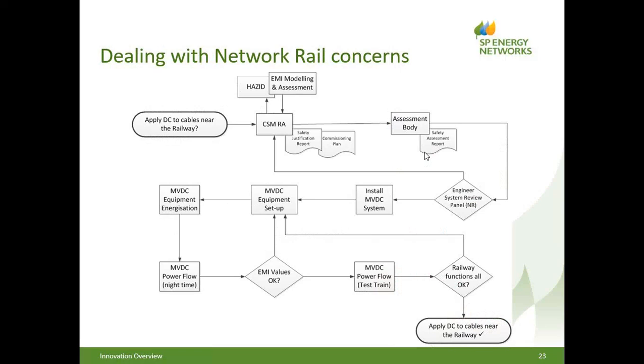So what we've got to do is undertake the common safety method risk assessment. That involves HazID workshops, and the output of this is to come up with a safety justification report, which also needs to include a commissioning plan of how we intend to bring the equipment online. And factoring into that very heavily is EMI modelling and assessment of the potential effects of the magnetic field and any potential cross-induction through the ripple effect of the harmonics that obviously will exist in the DC.